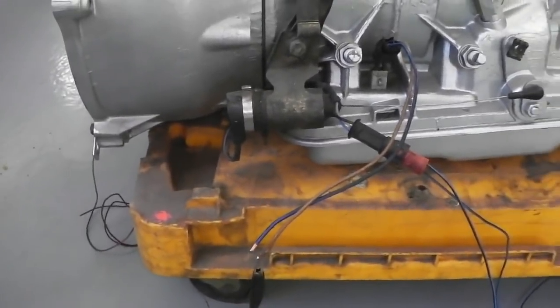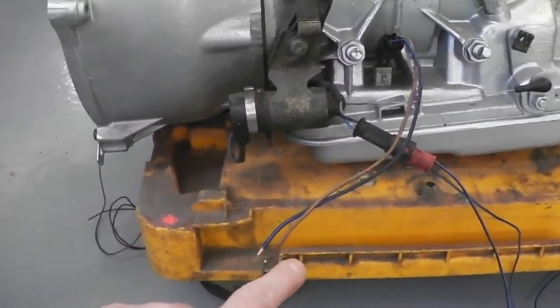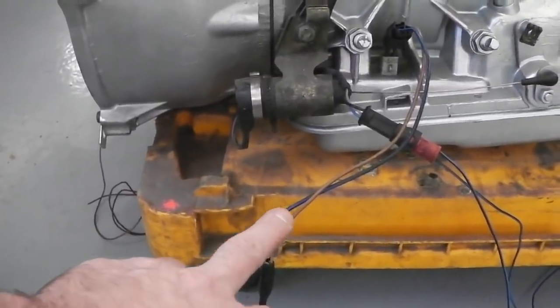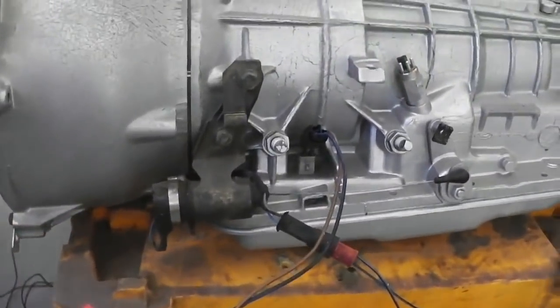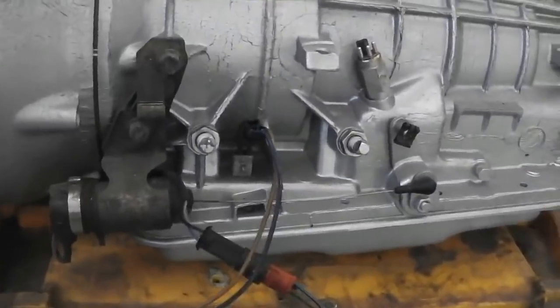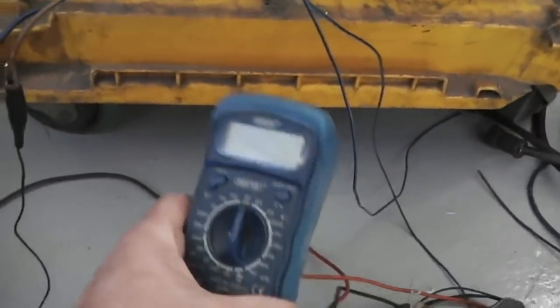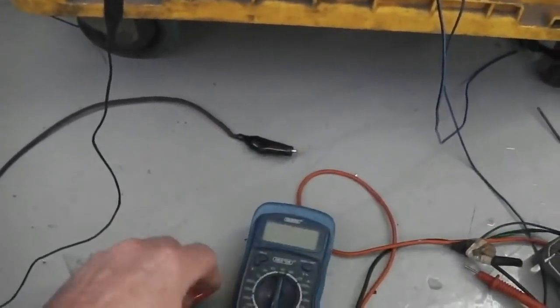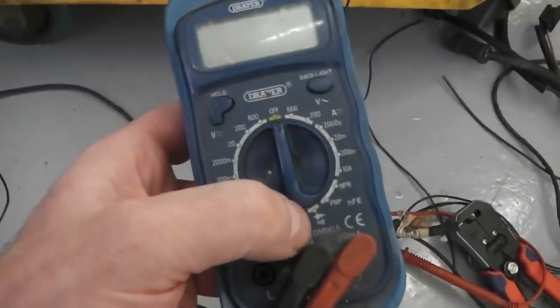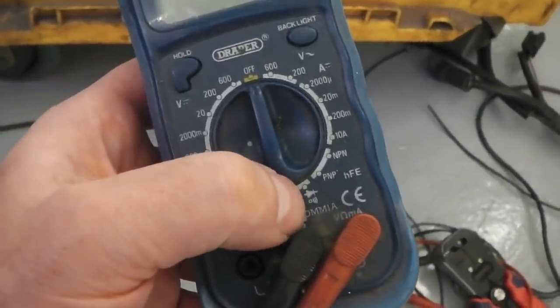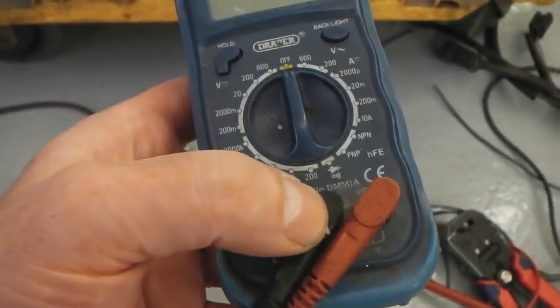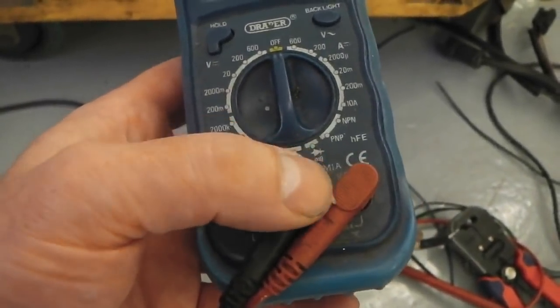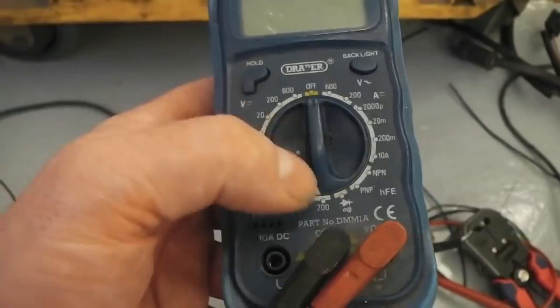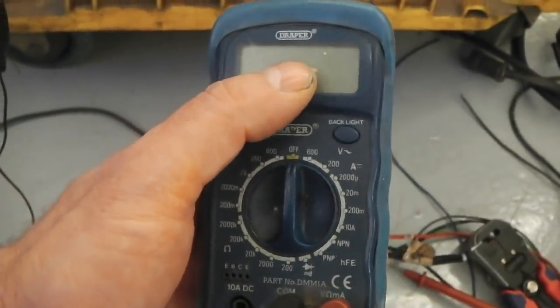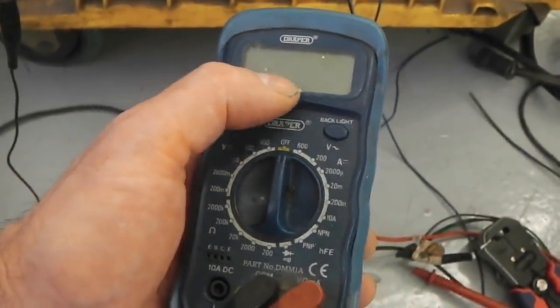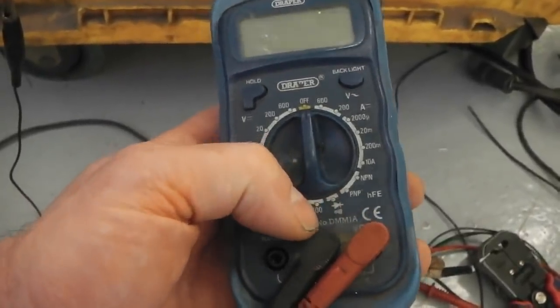Luckily brown is earth - could have been, it was a 50-50 chance which way round these went. Now I'll double check that you can diode these out with your meter. You have what's called Diode Test on your meter. If you ever got a meter and wonder what it is, when you put these test probes across a diode and you have it on that setting, you should get around 0.6, 0.7 reading on here, which is the volt drop across a diode.